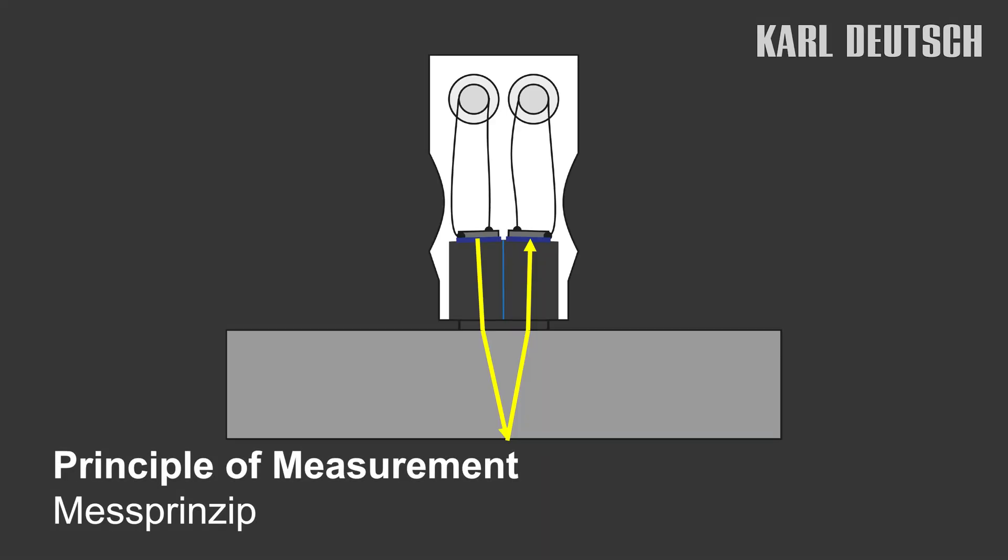The ECHOMETER works by means of an ultrasonic measurement. For the measurement, an ultrasonic probe is placed at the point to be measured. For this purpose, the probe must be coupled with a liquid or a gel.